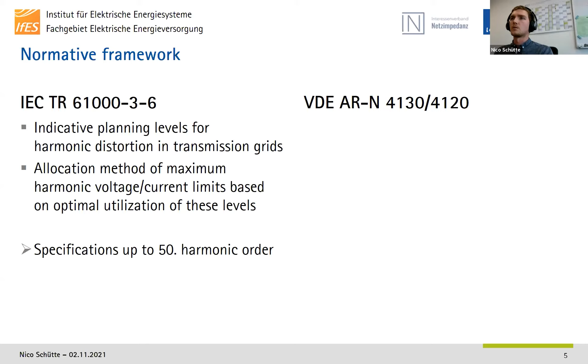So mainly there are 2 guidelines I'm currently working with. The one is IEC Technical Report 61000-3-6, which provides indicative planning levels for harmonic distortion in transmission grids. It also provides the allocation method to assign maximum harmonic voltage and current limits, and this is based on an optimal utilization of the planning levels provided in this guideline. The specifications are made up to 50th harmonic order. And that's the range where we're currently working when we're doing resonance analysis in transmission grids.